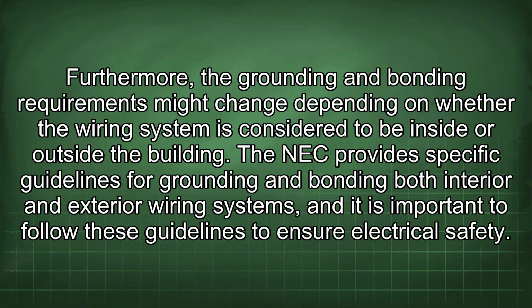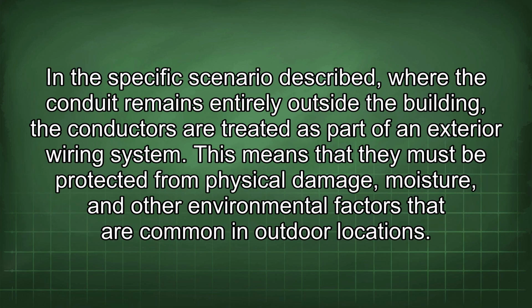Furthermore, the grounding and bonding requirements might change depending on whether the wiring system is considered to be inside or outside the building. The NEC provides specific guidelines for grounding and bonding both interior and exterior wiring systems, and it is important to follow these guidelines to ensure electrical safety. In the specific scenario described, where the conduit remains entirely outside the building, the conductors are treated as part of an exterior wiring system. This means that they must be protected from physical damage, moisture, and other environmental factors that are common in outdoor locations.